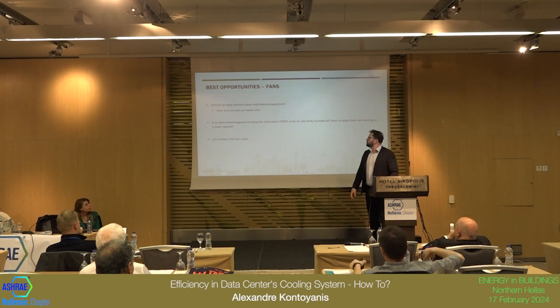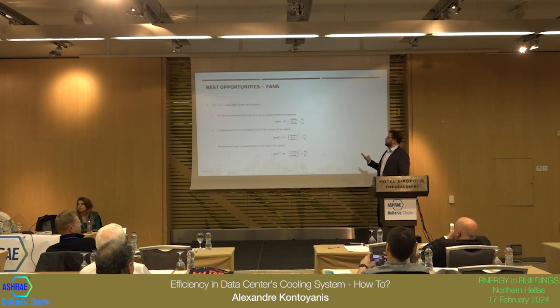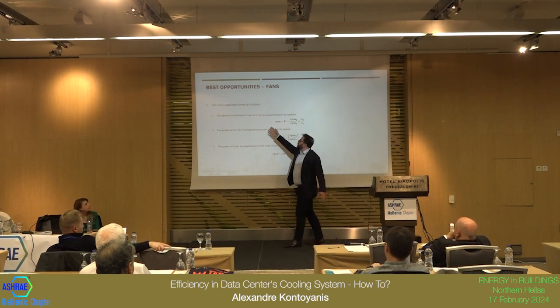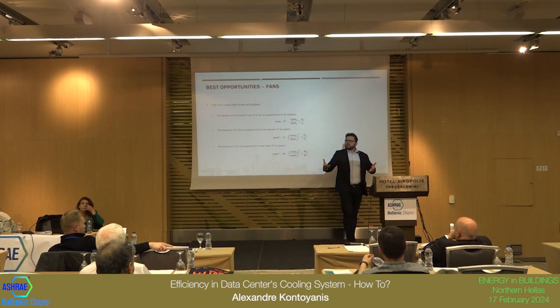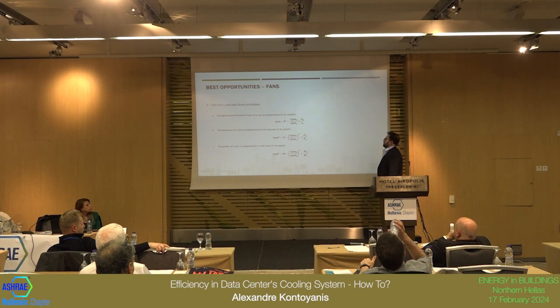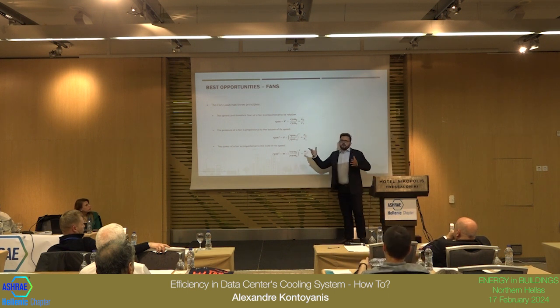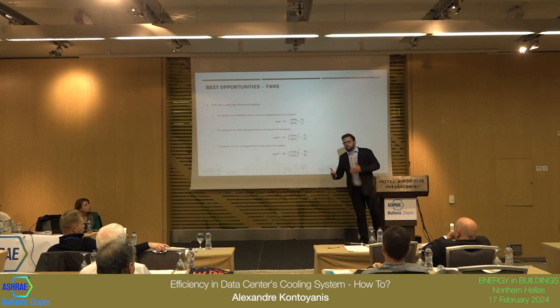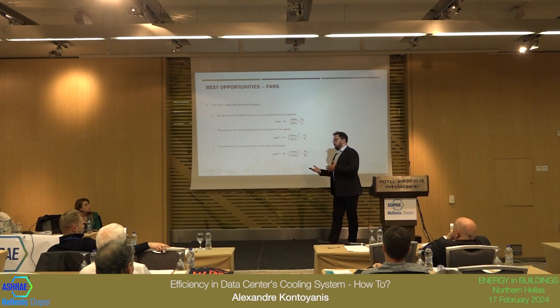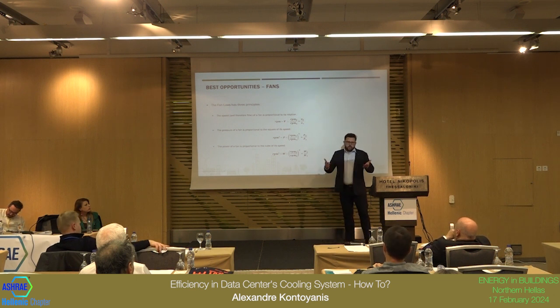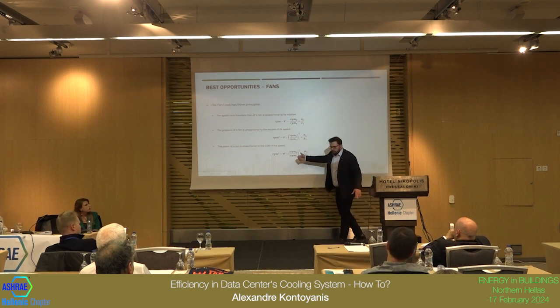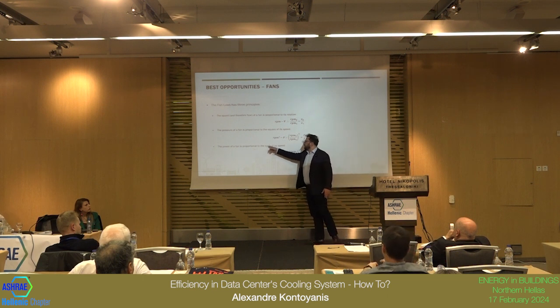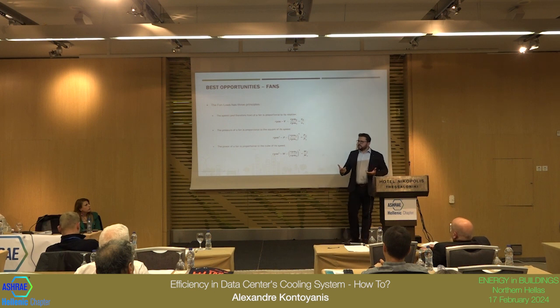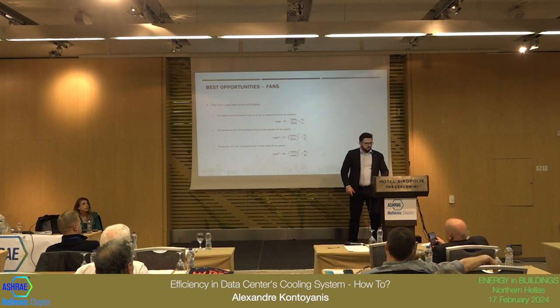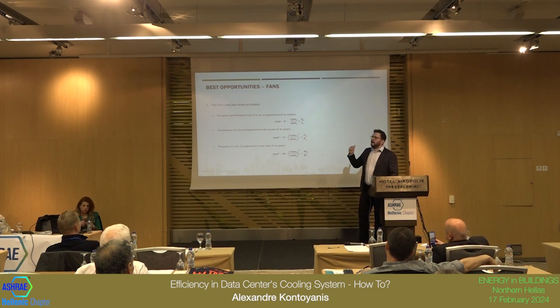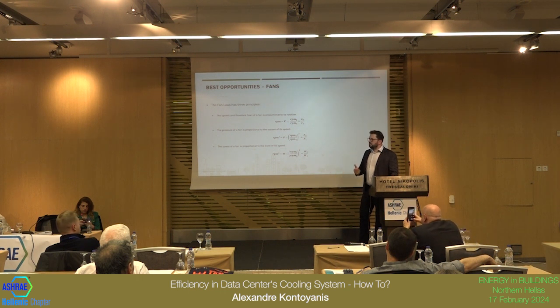Let's check the fan laws. The fan laws are basically three laws. The speed, therefore the flow of the fan, is proportional to the rotation. So if you double the rotation, you double the flow. Very simple. The pressure of a fan is proportional to the square of the speed. It means if you double the speed of your fan, you multiply the pressure by 4, and if you halve the speed, you divide the pressure by 4. And the power, therefore the energy consumption of a fan, is proportional to the cube of the speed. If you double your speed, you multiply your consumption by 8. Therefore, if you halve the speed of your fan, you divide your consumption by 8.